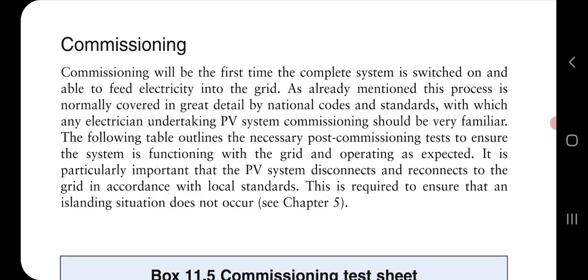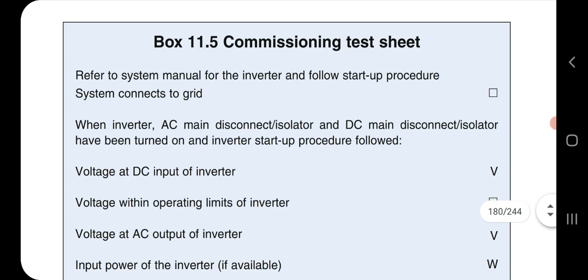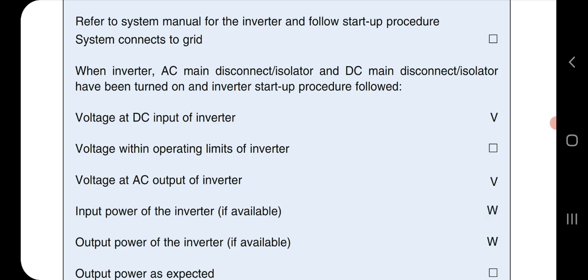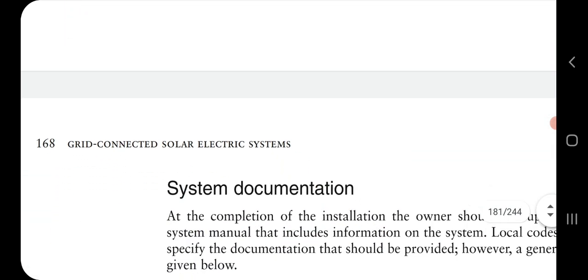Commissioning is the process where, after checking everything, we switch on the PV system and electricity is supplied to the grid. They have to abide by the national codes and standard codes for this, and the electrician should take care that everything is completed as per the testing sheet given. Here you can see the commissioning test sheet, with a lot of things. When the inverter AC main disconnector, isolator or DC main has been turned on and the inverter starts up, the voltage at the input and at the output of the inverter, and various things, have to be considered.